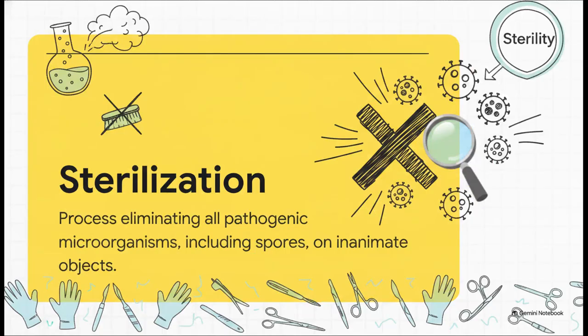So, the crucial point here is understanding the absolute difference between just cleaning something and actually making it safe for surgery. We've got to separate disinfection from true sterilization. While disinfection heavily reduces pathogens, and hey, it's great for a lot of surfaces, true sterilization is a much, much higher bar. It guarantees a complete sterility assurance level. We're talking about completely obliterating all microbial life, even those incredibly stubborn bacterial spores. It's not just about being clean, it's about absolute, calculated biological absence.